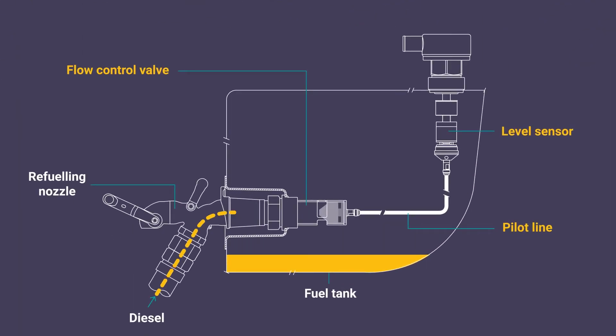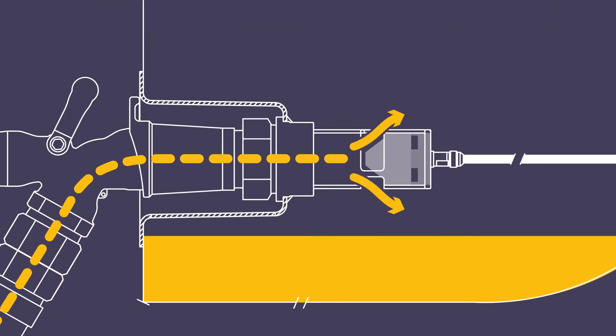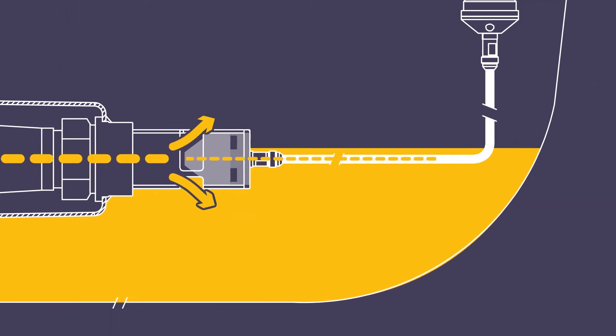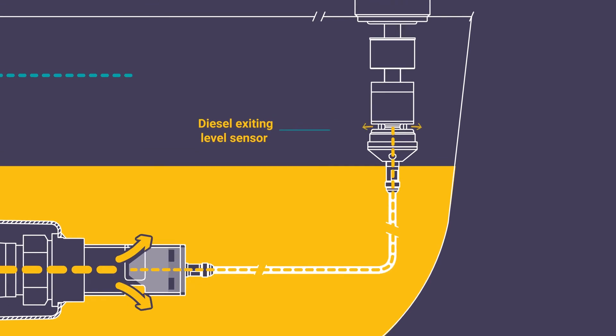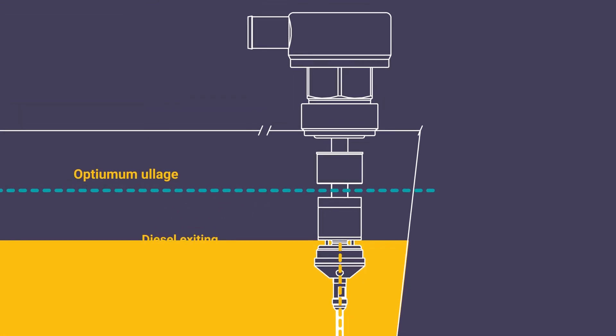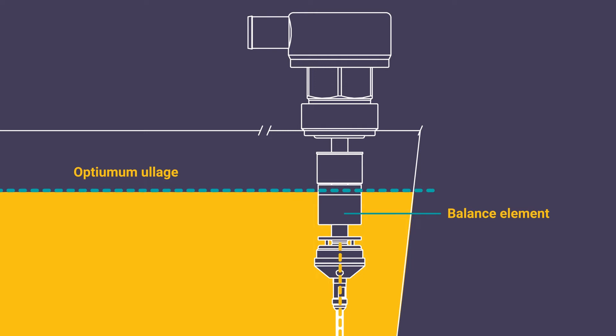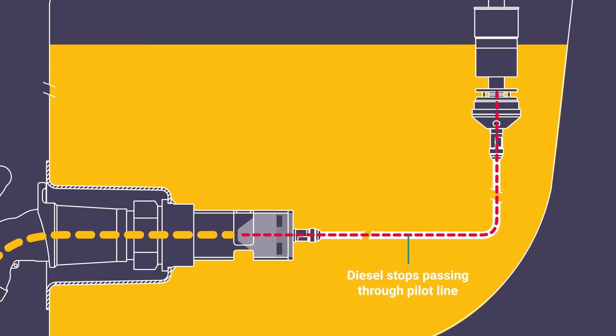Diesel from the pump passes through the selected filling hardware and then efficiently passes through the flow control valve into the tank. A trickle of diesel travels from the flow control valve through the pilot line and out of the bottom of the level sensor. When diesel within the tank reaches the optimum ullage, it interacts with a balance element in the level sensor.